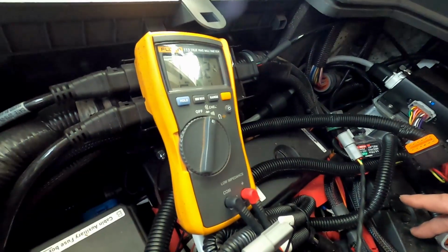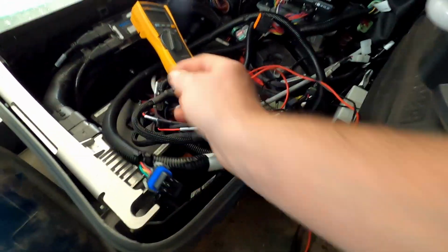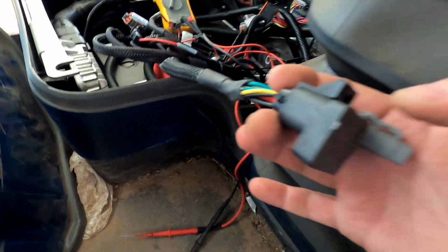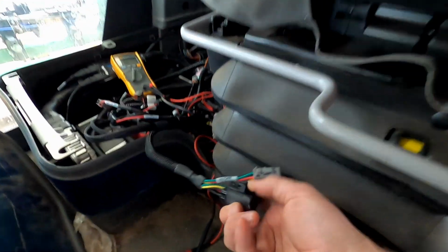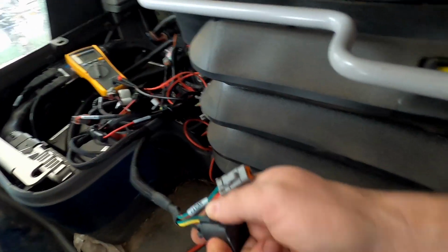You can see the bus is being powered up from the implement connector back there. So that means that we don't need this one to have power. This will get powered up by the whole bus. So I'm going to remove these wires out of here. Pull that out of there. Stick you up here for a second.